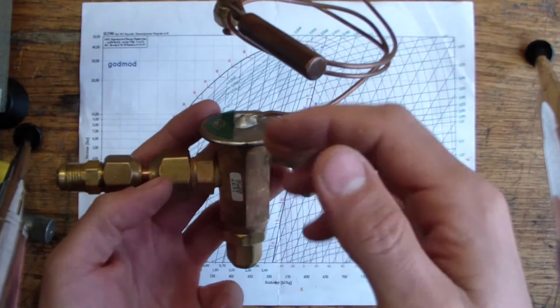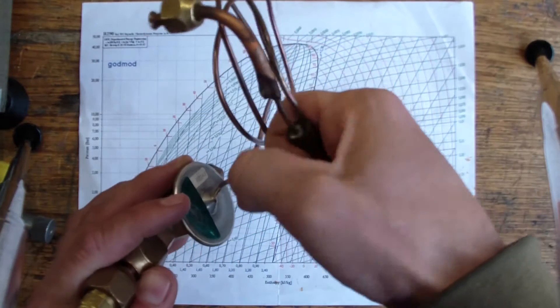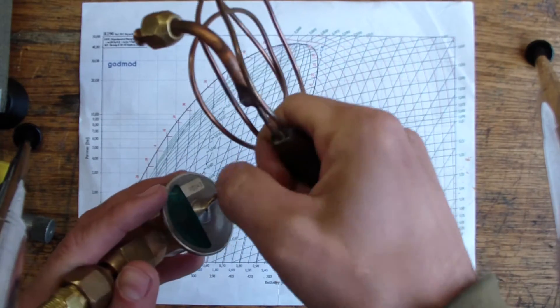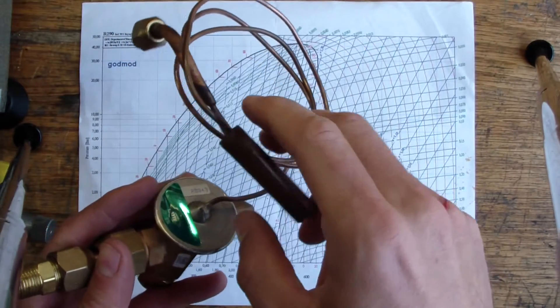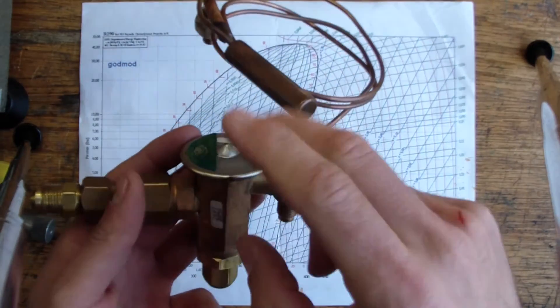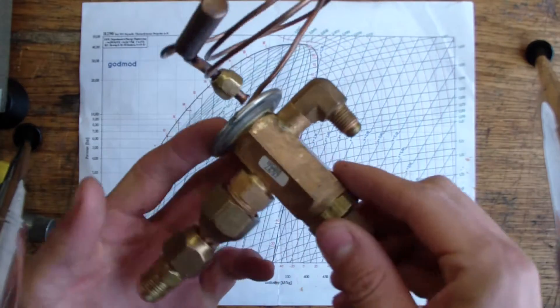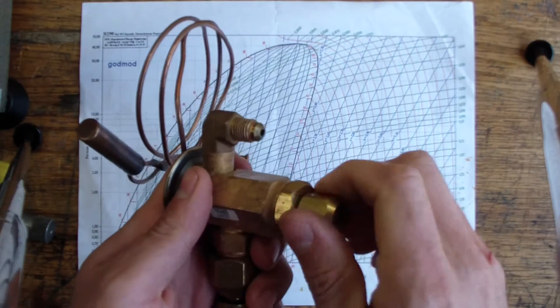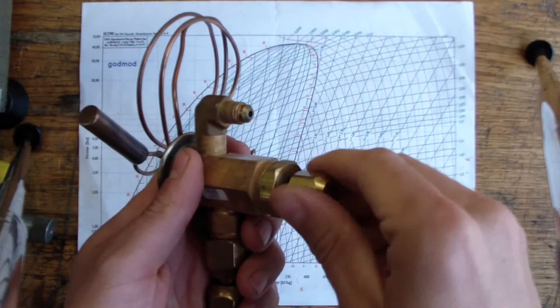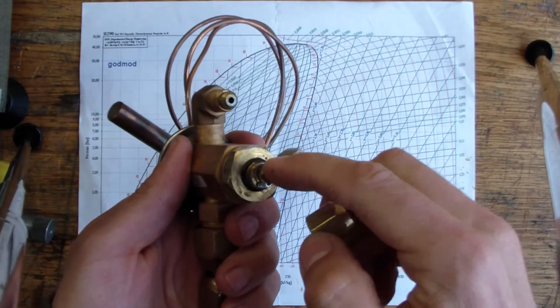Until the evaporator is properly fed, the suction line temperature drops, the temperature of the sensing bulb drops, saturation temperature inside the system drops. The diaphragm is allowed to retract by the spring applying pressure to it. The amount of superheat that's designed for the system can be adjusted to some extent with this superheat control.